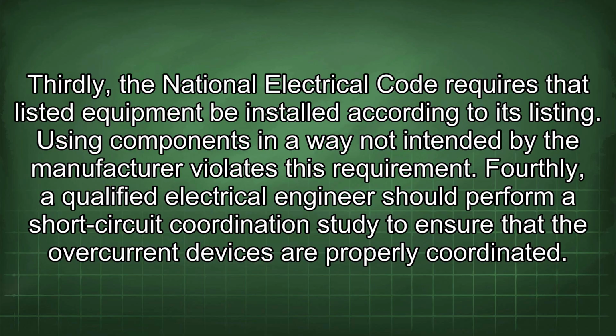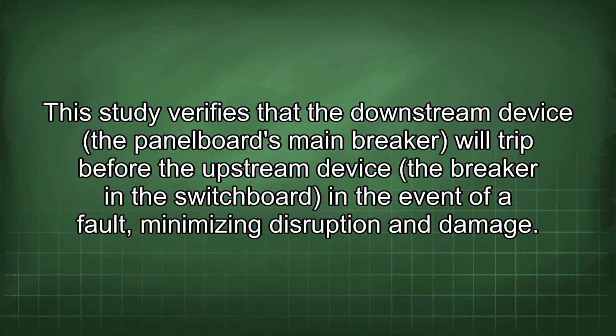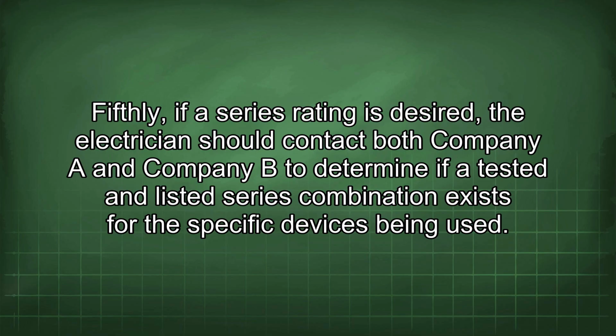Fourthly, a qualified electrical engineer should perform a short-circuit coordination study to ensure that the overcurrent devices are properly coordinated. This study verifies that the downstream device, the panelboard's main breaker, will trip before the upstream device, the breaker in the switchboard, in the event of a fault, minimizing disruption and damage. Fifthly, if a series rating is desired, the electrician should contact both Company A and Company B to determine if a tested and listed series combination exists for the specific devices being used.